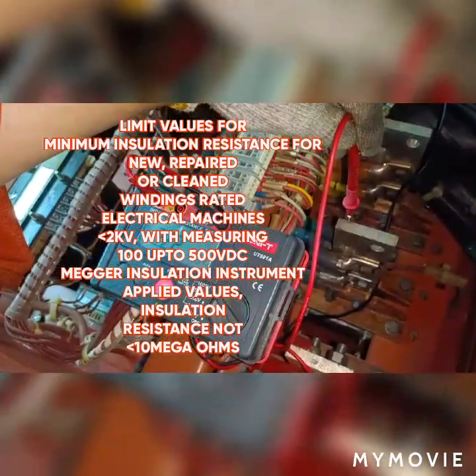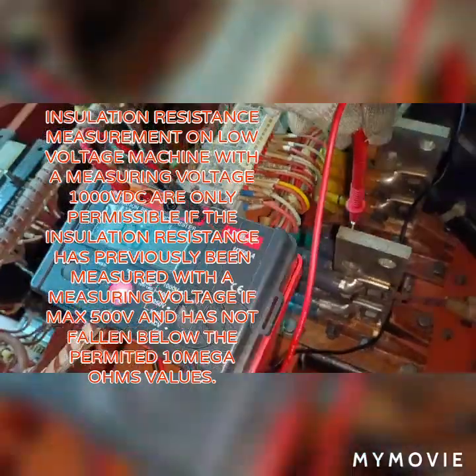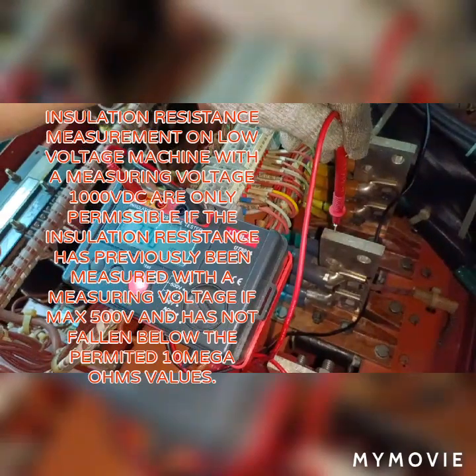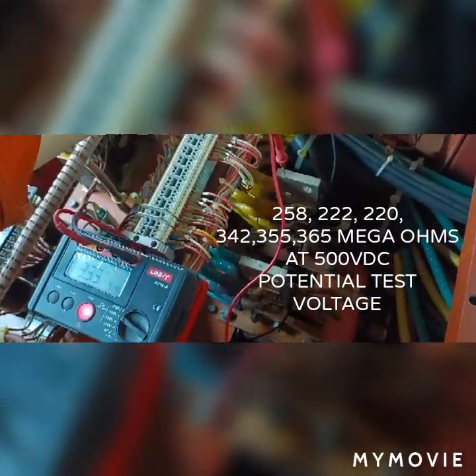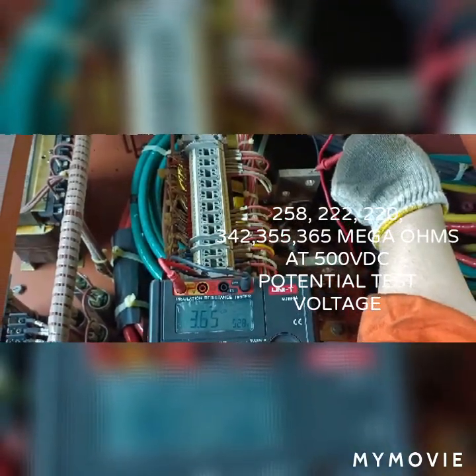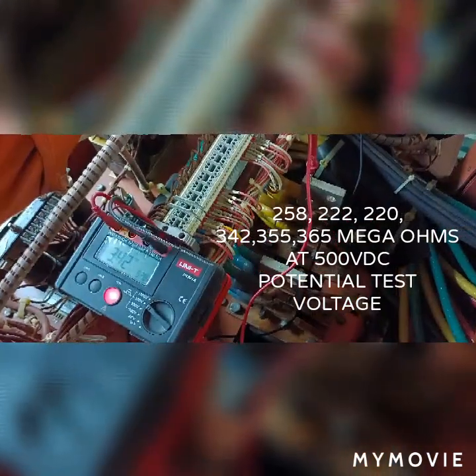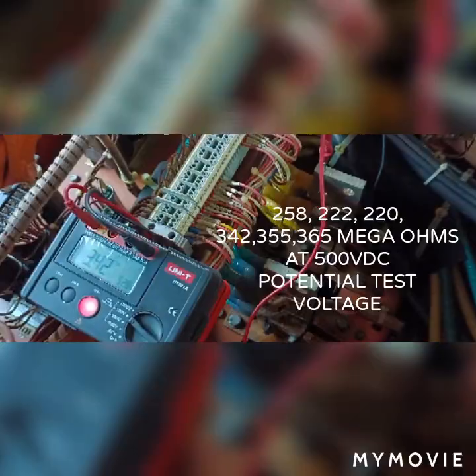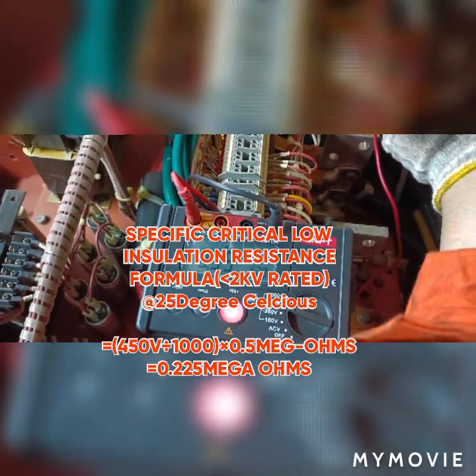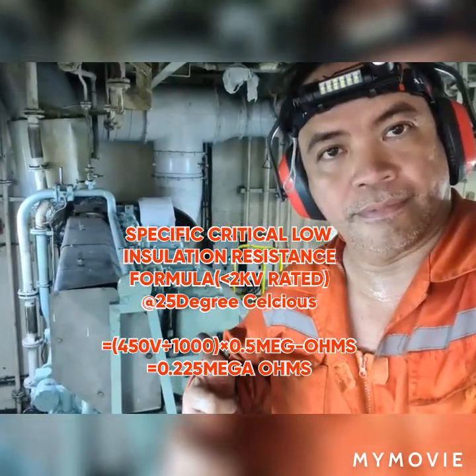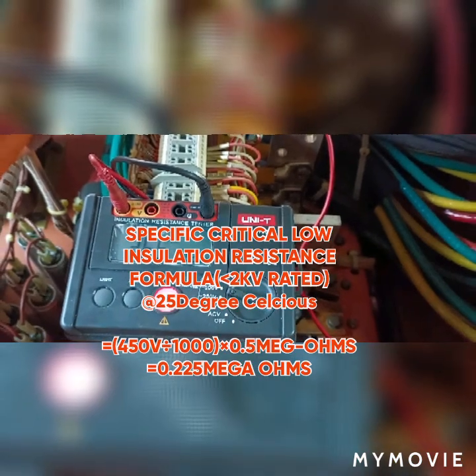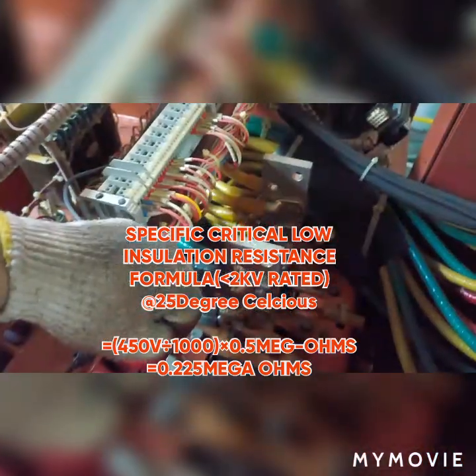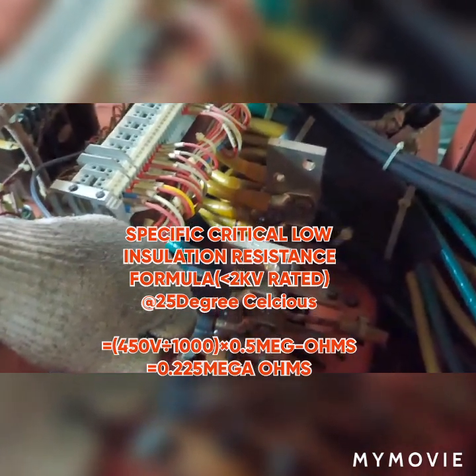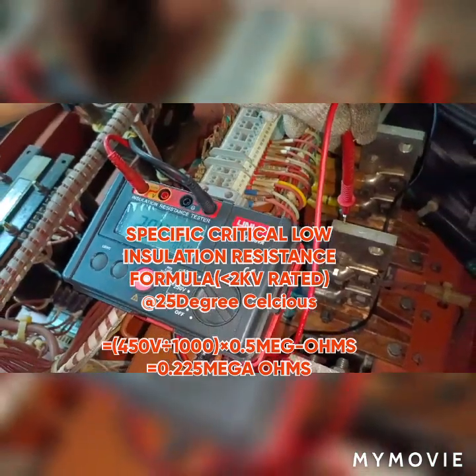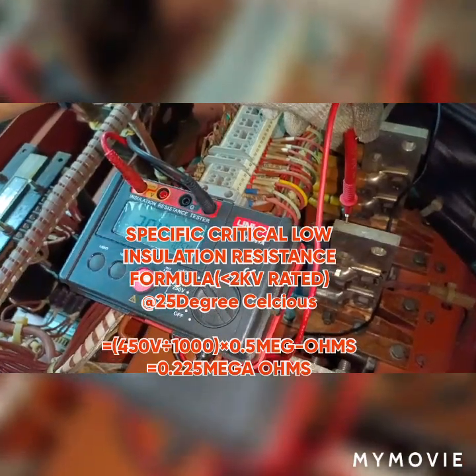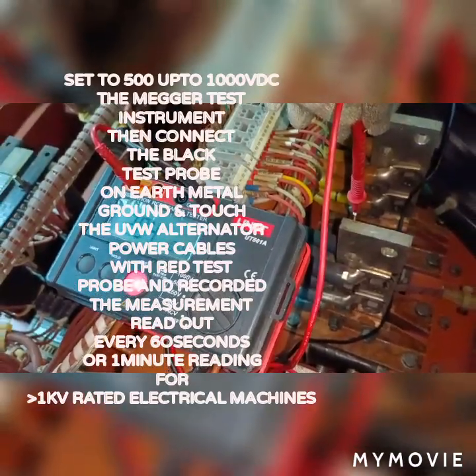For electrical machines less than 2000 volts or 2 kV, the applicable test potential voltage that you may apply ranges from 100 VDC to 500 VDC, and the critical insulation value is computed by 450 volts divided by 1000 and multiplied by 0.5 megaohms per kilovolt, and that is your critical insulation resistance. Normally, for low voltage machines less than 2 kV, the insulation minimum value is 10 megaohms.